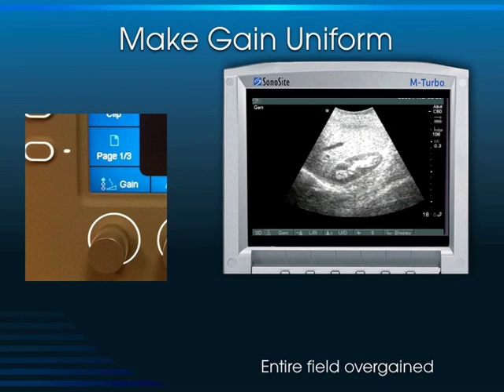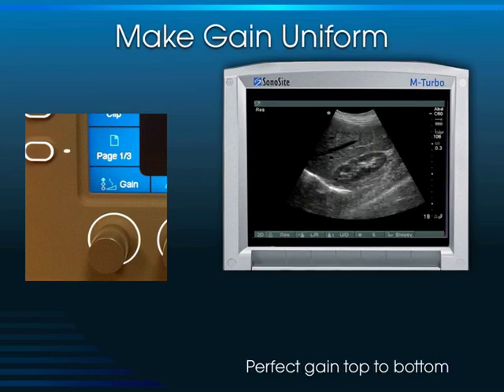To adjust the gain, use the rotary knob on the SonoSite device — turn it counterclockwise. As we do so, we take this severely over-gained image down to a nice level of gain where you can easily see that the cortex of this kidney is less echogenic than the liver parenchyma.